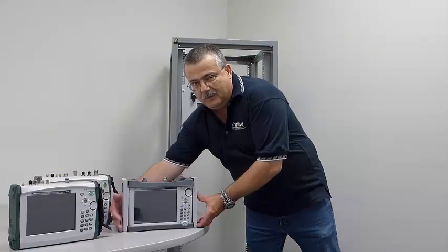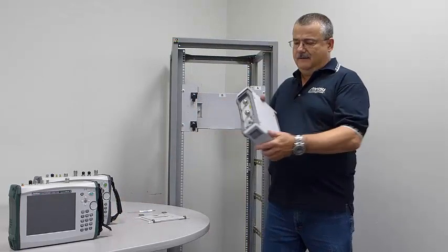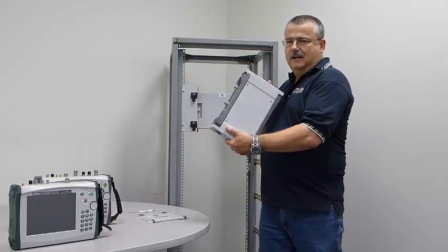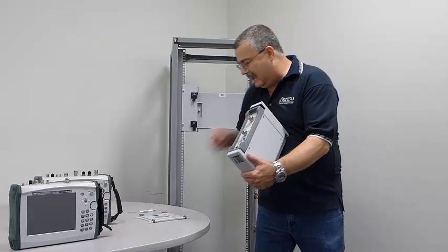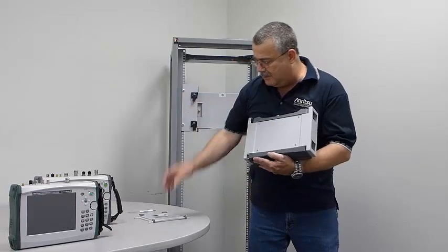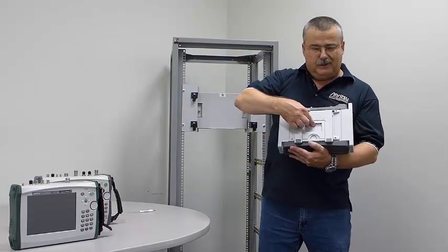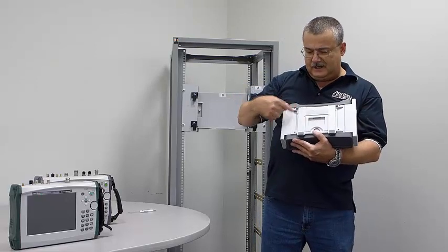All right, so what we've done now is we've gone ahead and we pre-installed the bracket C onto the back of the economy instrument. And that was done simply by removing the factory installed steel bail handle, which is normally here. It's held on with four screws.